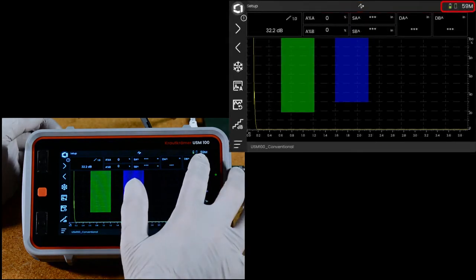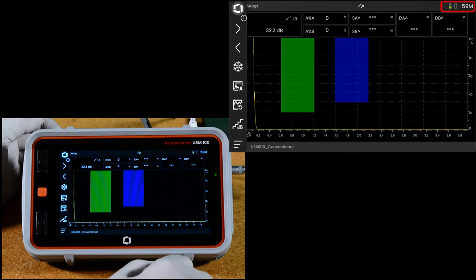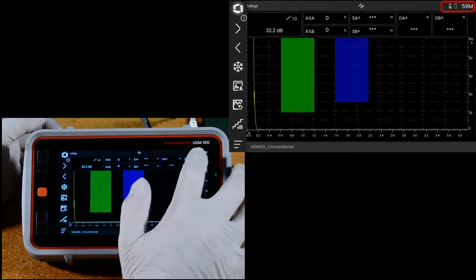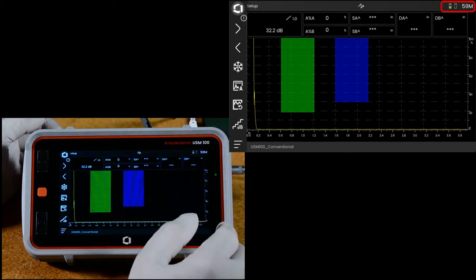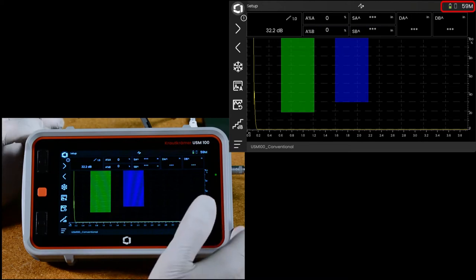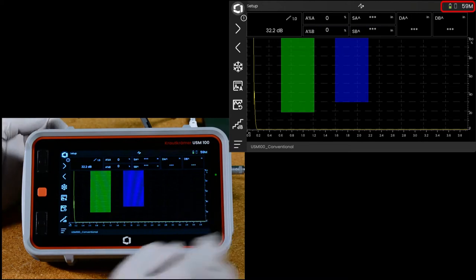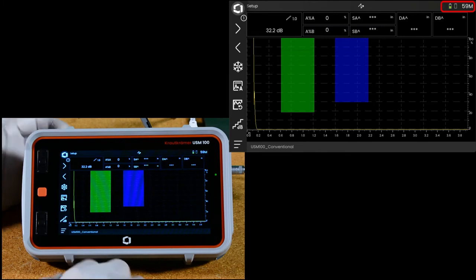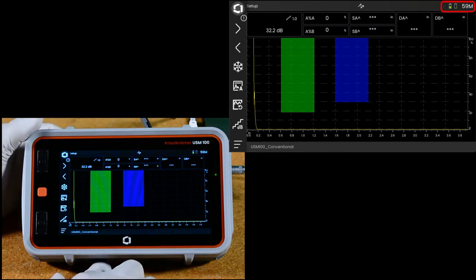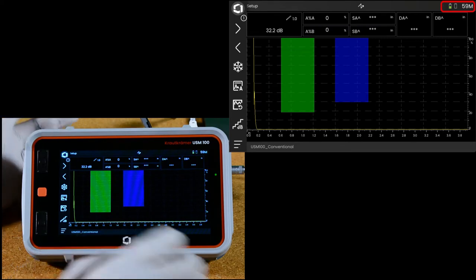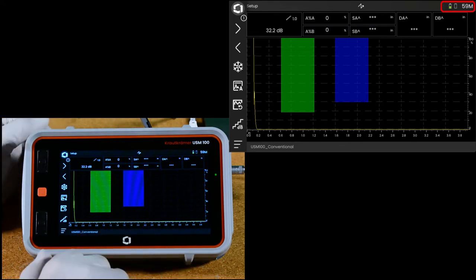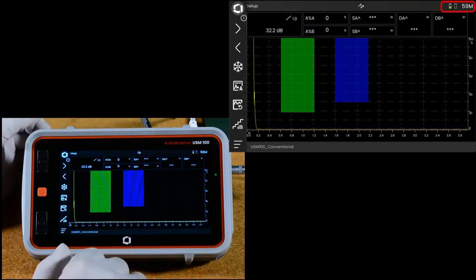Over here in the upper right hand corner is the battery status monitor. There are two little graphical indicators, one for each of the batteries. There are two batteries in this instrument. One is built in permanently. The other is accessed through a door here on the bottom. You can hot swap that one. While the instrument is in operation, you can open the door, pull that battery out, put in a freshly charged battery, and you're ready to continue operation.